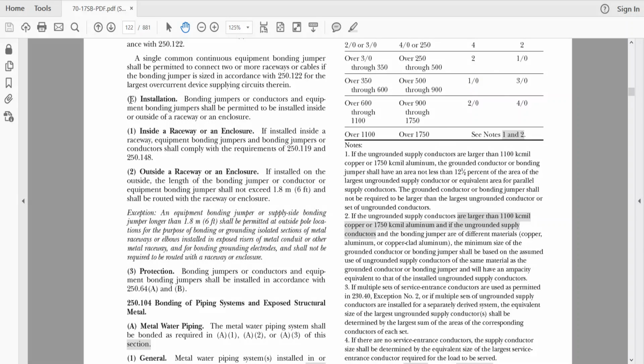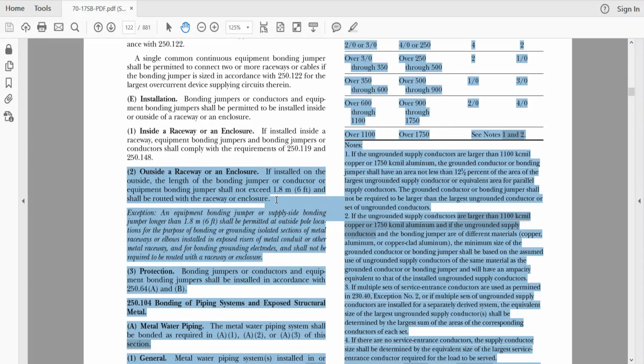250.102E. This E is what we're dealing with here. It's using that last example we had, okay? When they're run outside of the raceway or enclosure, now I want you to understand that E deals with both. It doesn't matter whether it's the supply side or the load side. This is dealing whether you're running it inside the raceway or you're running it outside the raceway. If you're running it outside the raceway, again, we're talking about bonding jumpers or conductors and equipment bonding jumpers shall be permitted to be installed inside or outside of the raceway. And if it is outside, like the example, the picture we just showed, it says if installed on the outside, the length of the bonding jumper or conductor or equipment bonding jumper shall not exceed 6 feet and be routed with the raceway or enclosures.